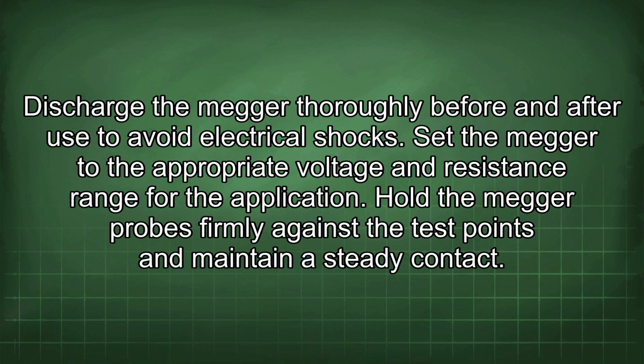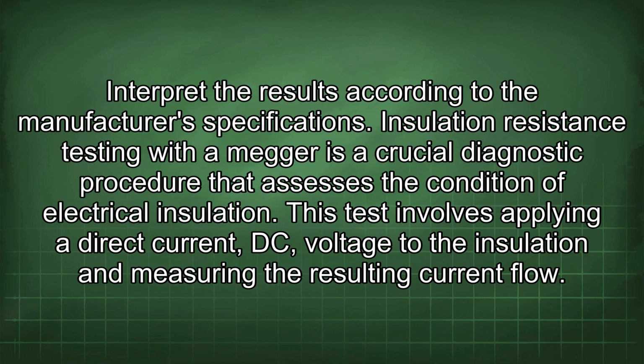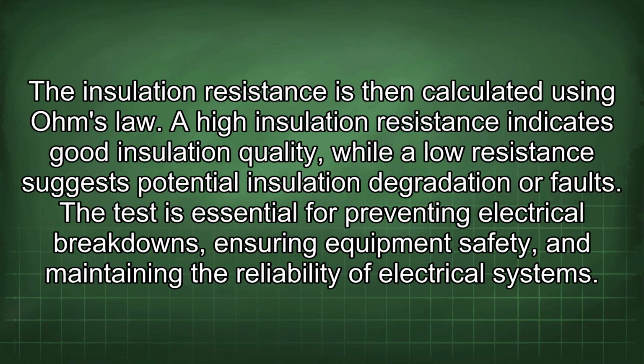Set the Megger to the appropriate voltage and resistance range for the application. Hold the Megger probes firmly against the test points and maintain a steady contact. Interpret the results according to the manufacturer's specifications. Insulation resistance testing with a Megger is a crucial diagnostic procedure that assesses the condition of electrical insulation. This test involves applying a direct current (DC) voltage to the insulation and measuring the resulting current flow. The insulation resistance is then calculated using Ohm's law.